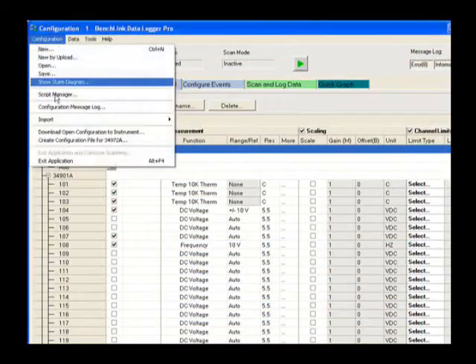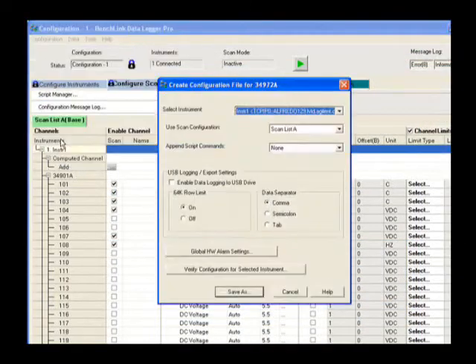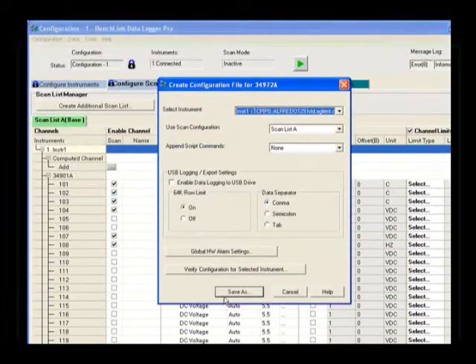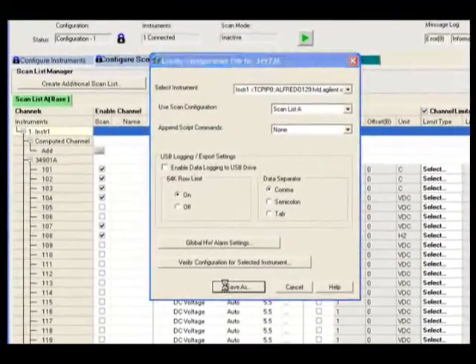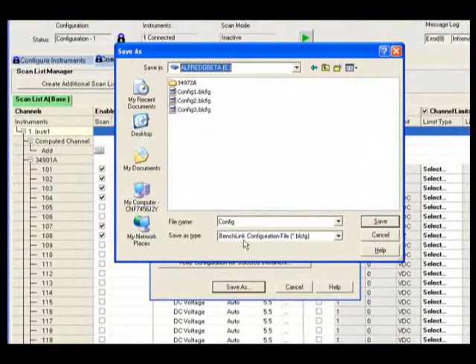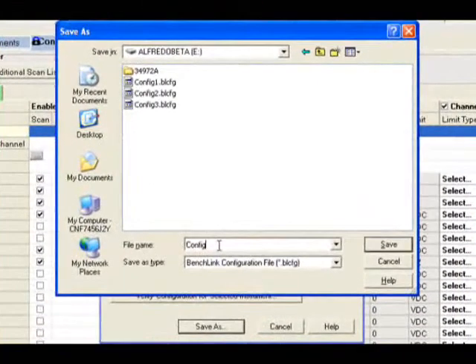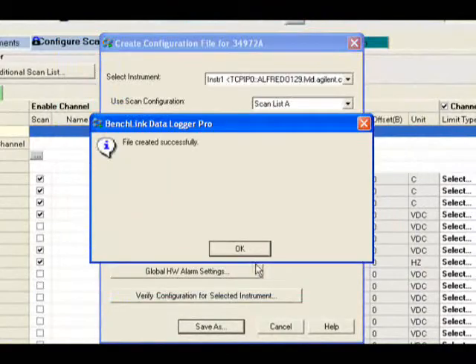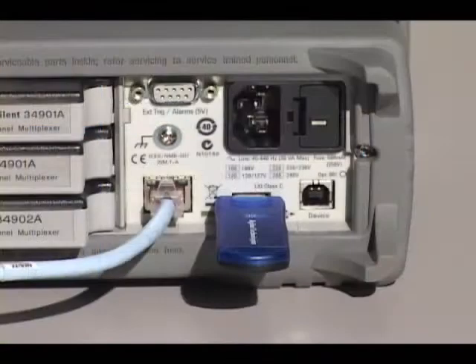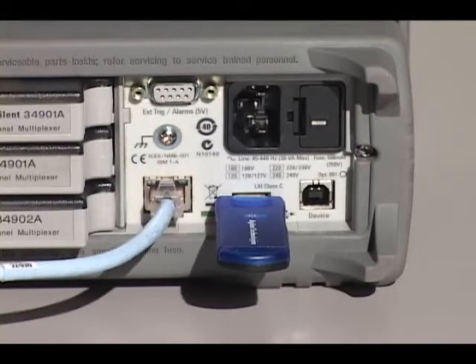And when you're not connected to a computer, simply copy your BenchLink data logger configuration to the USB flash drive. Upload it to the instrument, and then log data directly to your USB stick.